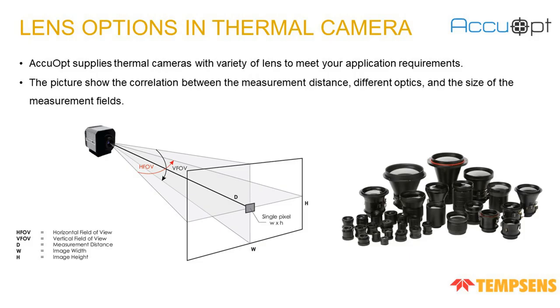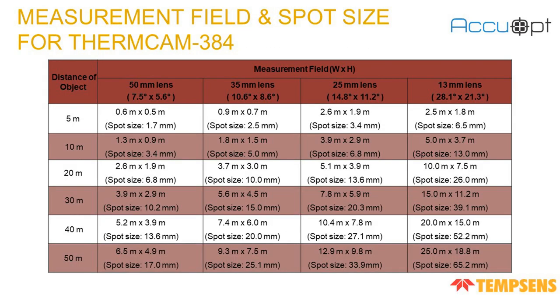Our thermal camera comes with different lens options, which we can select depending on the number of components to be measured and the size of your yard. This is the measurement field and spot size for the ThermCam 384. As you can see, with a 50 mm lens at 30 meter distance, the camera will cover a 3.9 meter by 2.9 meter area with a spot size of 10.2 mm. With a 25 mm lens, we can cover a 7.8 meter by 5.9 meter area with a spot size of 20.3 mm.